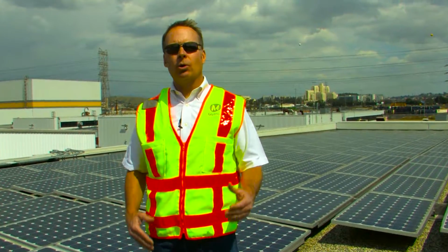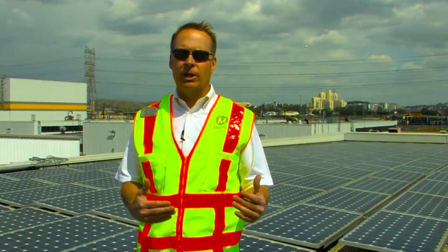As electricians, you are well trained and very familiar with the hazards of working with electrical current. However, there are some hazards that are very specific to photovoltaics or to solar systems. And primarily it is direct current. Direct current is a constant level with a constant voltage, never passes through zero like alternating current does. As such, the arcs are hotter and they're longer sustained and they never go off.